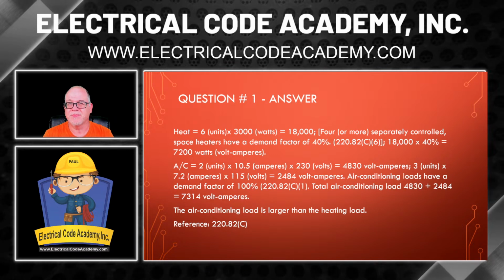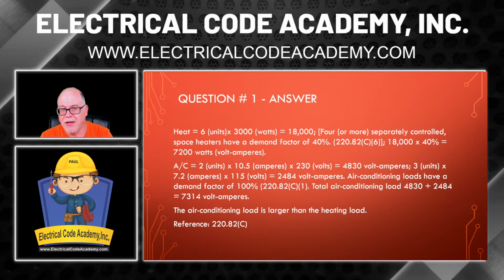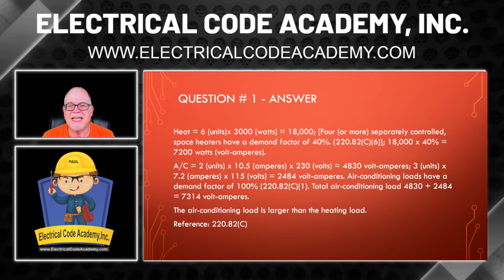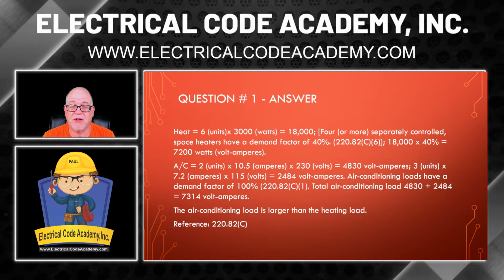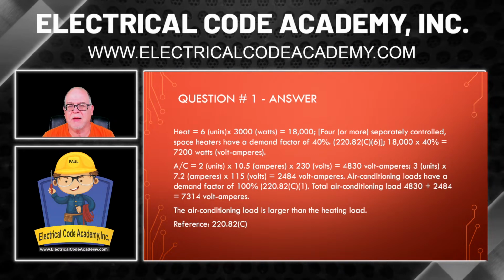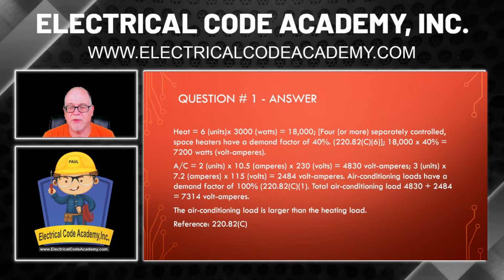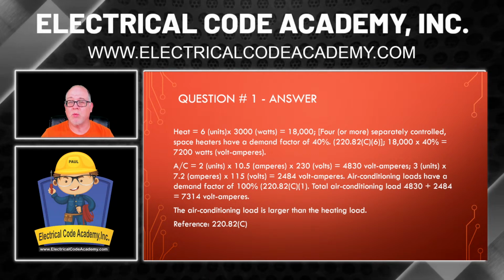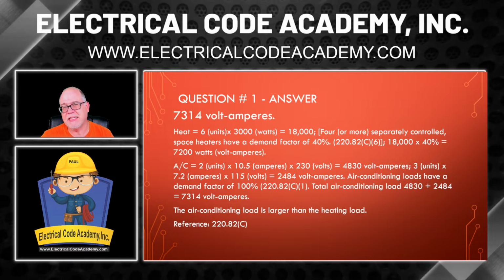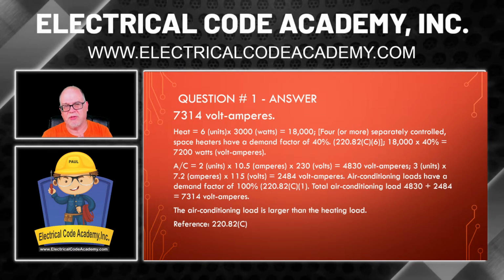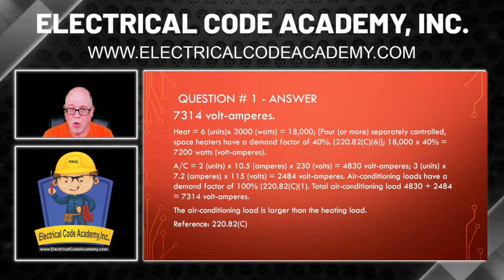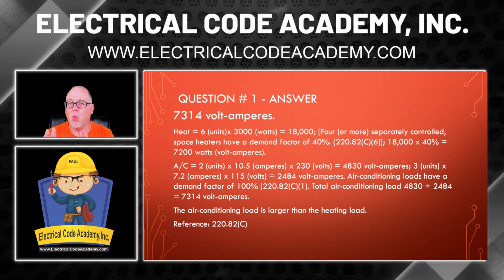Well, guess what? The AC is larger than the heat. In fact, it's 114 VA or watts greater for the AC over the heat. So which one wins? Obviously, the AC is going to win. So the answer is 7,314 VA or 7,314 watts.